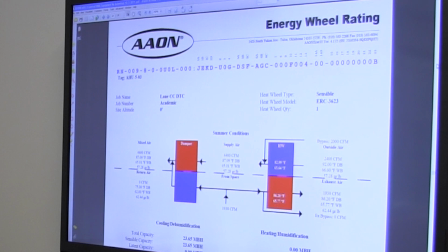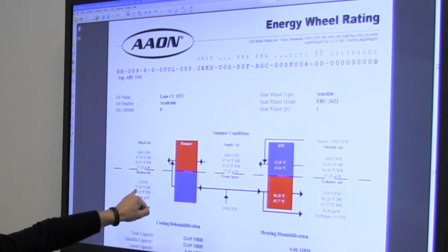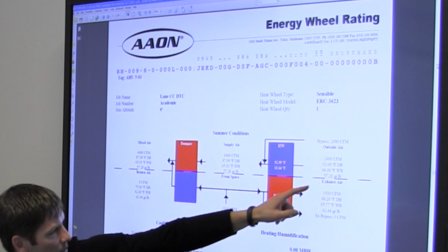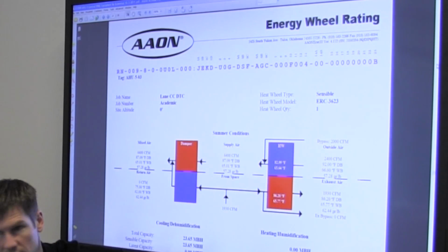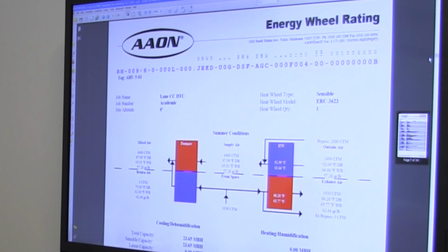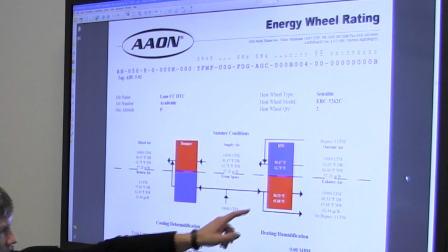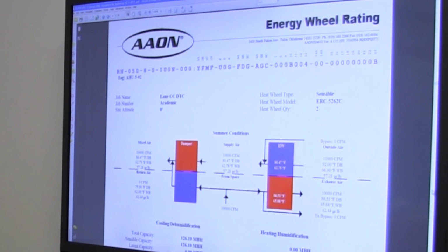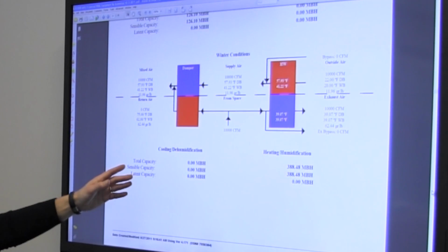And then on the cooling side, it takes 75-degree air out of the building. That will cool down 92 to 82. So you get 10 degrees of free cooling if you were at your peak and your building was indeed just 75 degrees. Whereas those larger units are even better. It's taking 92 degrees down to 80, so it's got 12 degrees on the cooling side. And on the heating side, it's 22 degrees up to 57 degrees, so quite a bit.